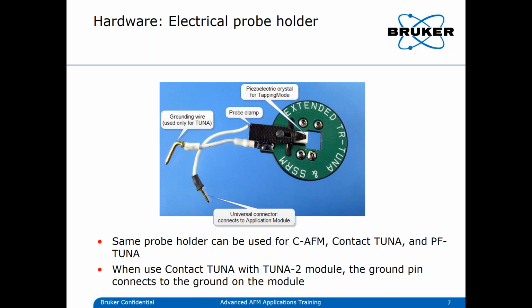This is the standard holder, or this is the holder for the measurements for the Icon system. I have a picture of the multimode holder later as well. One of the things that is also of importance here for the Icon is that this can be used if you go for laser alignment on the Icon system. And the software is asking you if you want to go to the alignment station. This has the same height dimensions as the standard holder, so you can also use the alignment station for the TUNA holder to align your laser on the cantilever.